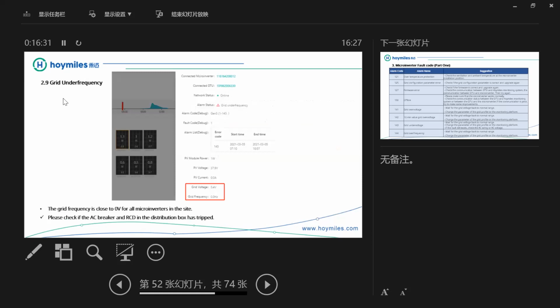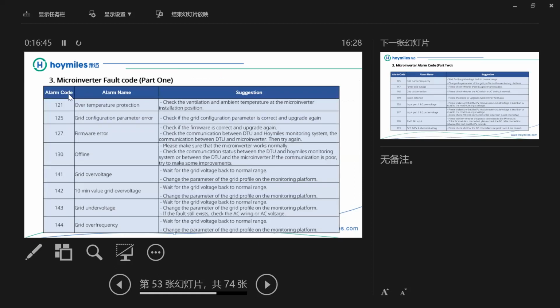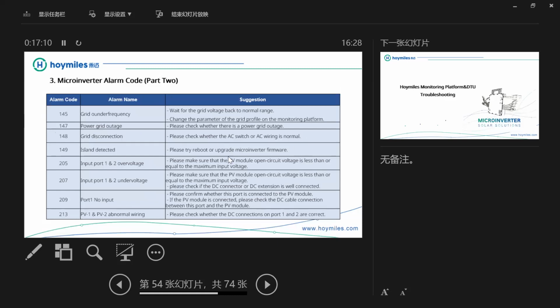If the alarm shows grid under frequency, where the grid frequency is close to 0 for our microinverter on the sites, please check if the AC breaker and the RCD in the distribution box have tripped. This table and the next table show all the alarm codes in the monitoring platform, and each code corresponds to one alarm name, and all of these codes constitute our monitoring system. You will also find this table in the user manual.